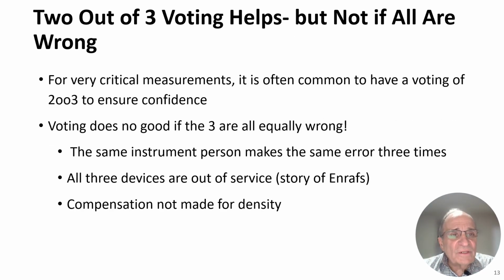Typically, for a critical measurement, we use a 2 out of 3 voting, which helps, but it does not help if all 3 of them are wrong. So if all 3 of them are calibrated for the wrong fluid, it's certainly not going to help you. But with a 2 out of 3 voting, you have 3 signals coming in, and if you see that 2 of them agree, you accept those 2 and you can ignore the third and have an instrument person check out that third to see why it's not reading properly. This voting does no good if all 3 are equally wrong. If all 3 are set up for the wrong fluid, that's certainly not going to help you.